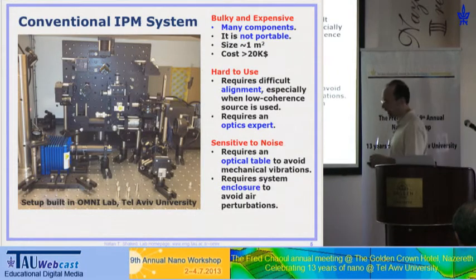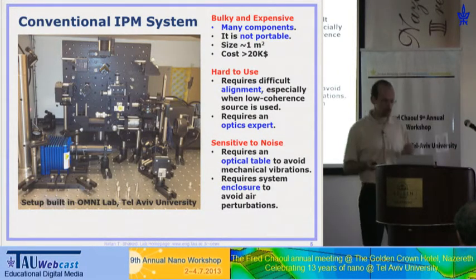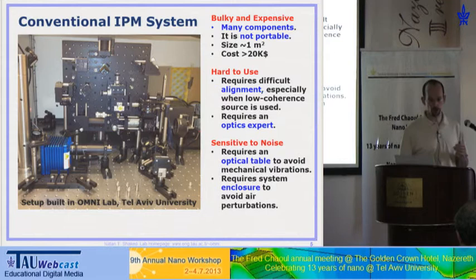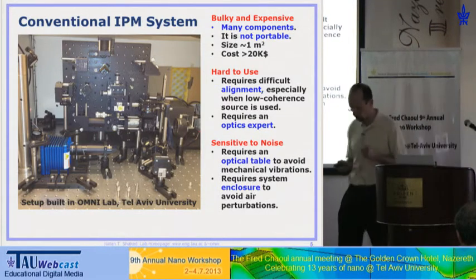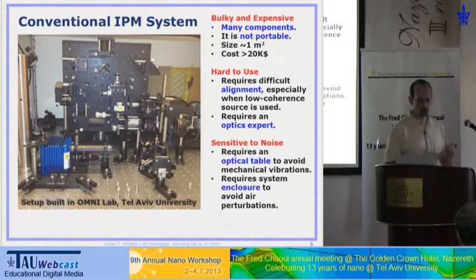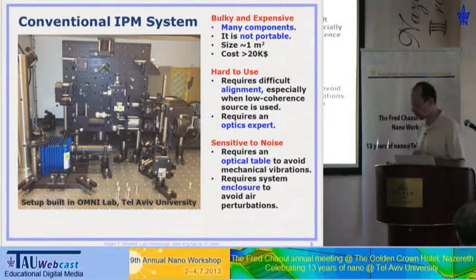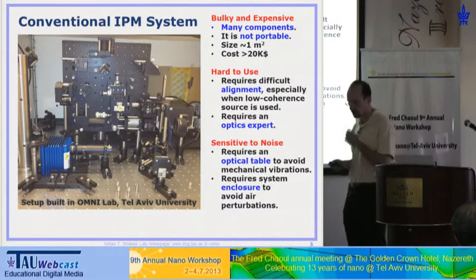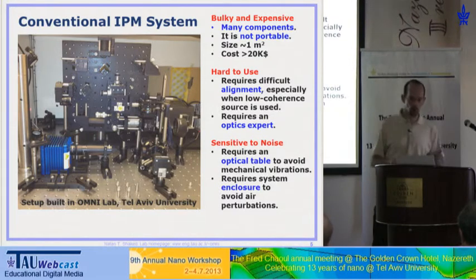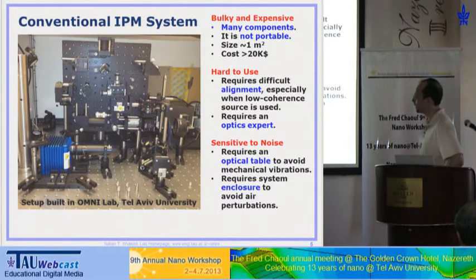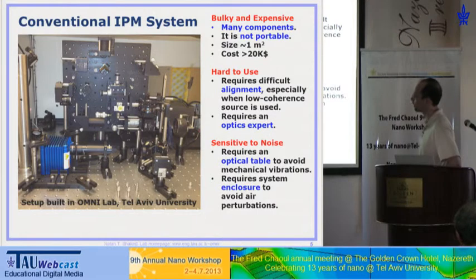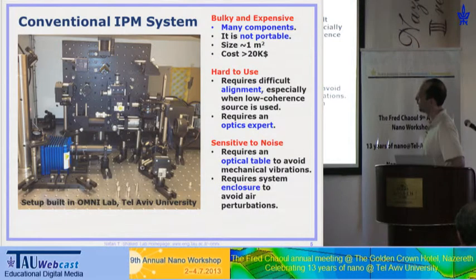The problem — and I think this is one of the reasons these systems didn't get into the clinics as expected compared to other microscopy techniques — and also for low-resource industry use, is that these systems are quite big, bulky, and expensive. This is the first system built in my lab. It's a Mach-Zehnder interferometer with a beam splitter, another beam splitter, two microscope objectives, and two mirrors. The beams come from a low-coherent laser.